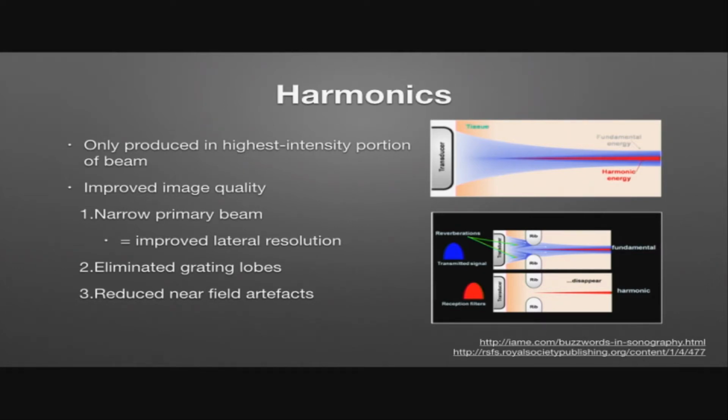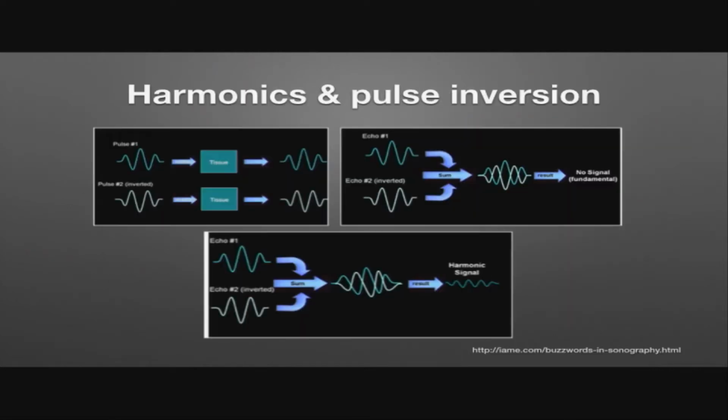But we said that the axial imaging was a problem, and this is obviously extremely important. Well, the way that we get around this is with what's known as pulse inversion. So we said that longer pulses were needed for bandwidth filtering, and that was going to reduce our axial resolution. And that was all because we wanted to have narrow bandwidths of the fundamental and the second frequency, so that we had to have that within the whole bandwidth. Well, a solution to this axial resolution degradation is to use this pulse inversion, and that's where we use 2 pulses per scan line rather than 1.